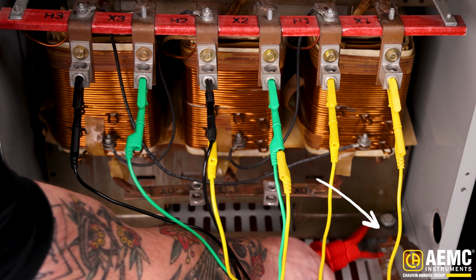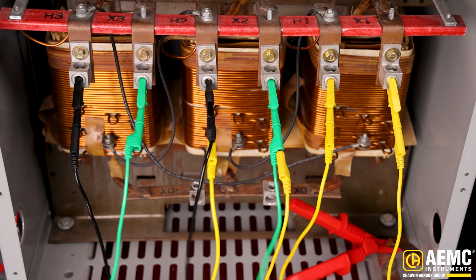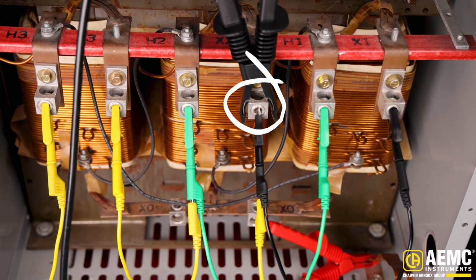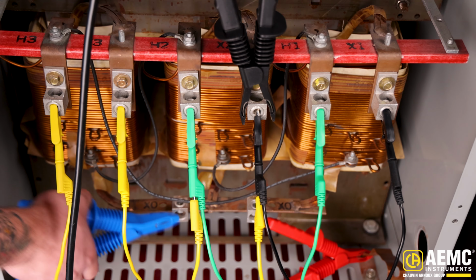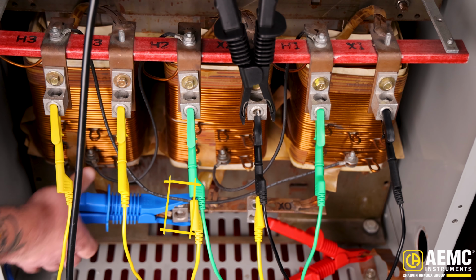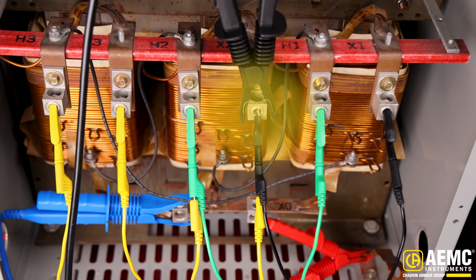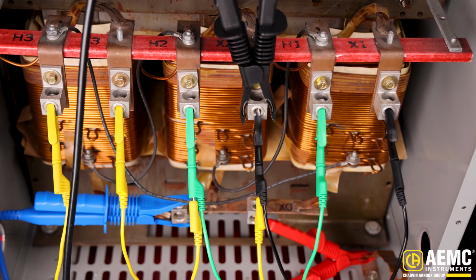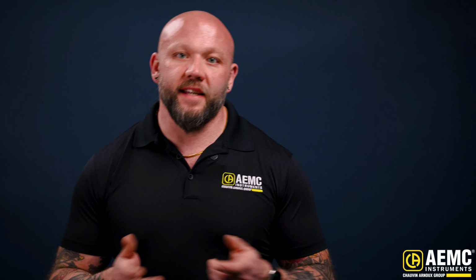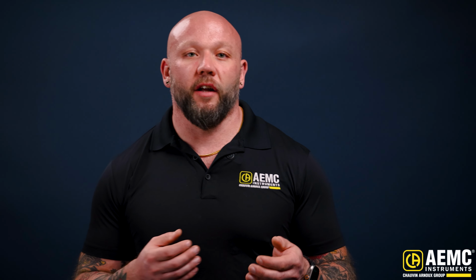Connect the red lead to the chassis ground of the transformer, and then connect the black lead to the primary windings and place the guard on the secondaries. In this example, we've shorted all three primaries together, as well as the secondaries, to test all three phases simultaneously.